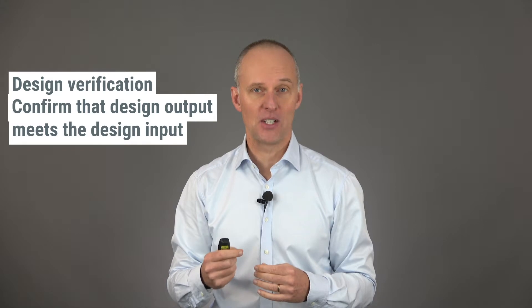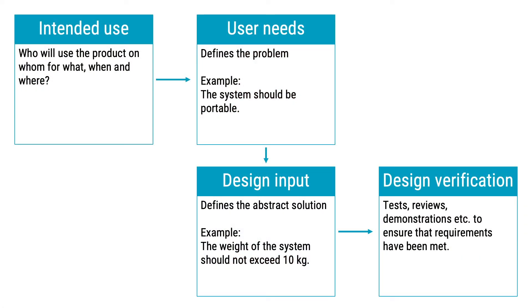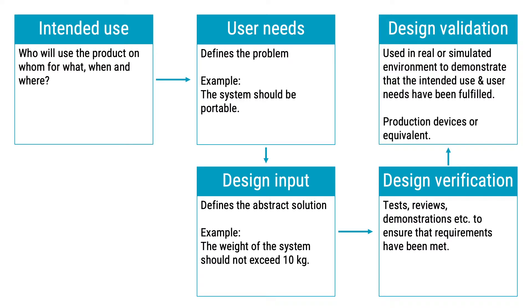In design control terminology, this is called design verification — confirming that design outputs meet design input requirements. In our example, the design input was that the device weight should not exceed 10 kilograms, and the verification could be done by putting the device on a calibrated scale and weighing it. You may use many different methods for verification, and which methods you use are in most cases up to you to decide. When you have verified the product meets technical requirements, you also have to check it meets the intended use and user needs — because a product may be 100% technically correct but still useless in a real setting.